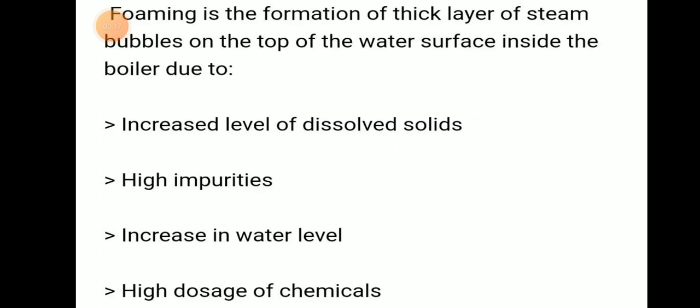Foaming is the formation of a thick layer of steam bubbles on top of the water surface inside the boiler. This may be due to increased level of dissolved solids (total dissolved solids), high impurities, increased water level, or high dosage of chemicals.